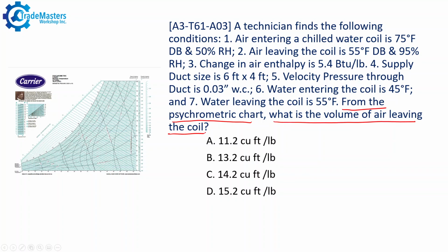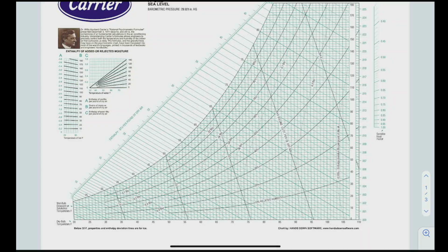So let's switch over to the psychrometric chart and just review the different pieces of information on the chart that are useful to us. Basically, to use a psychrometric chart, you only need two conditions of air, any two that are plottable, and you can interpret all kinds of other information about the air from the chart. For instance, if you know the wet bulb and dry bulb temperature of air, from that you can determine its specific volume, its relative humidity, its BTU content, etc.